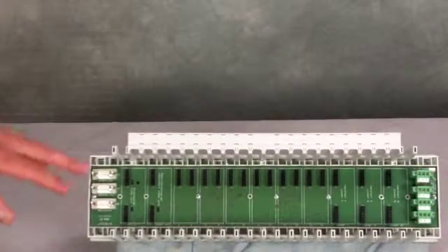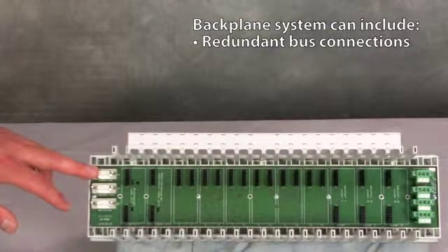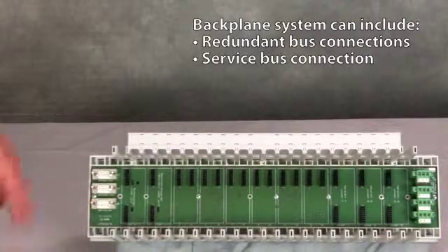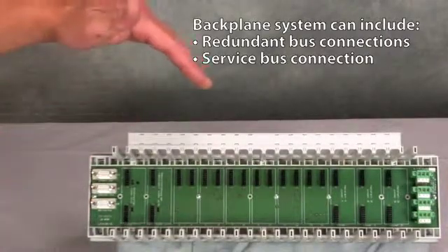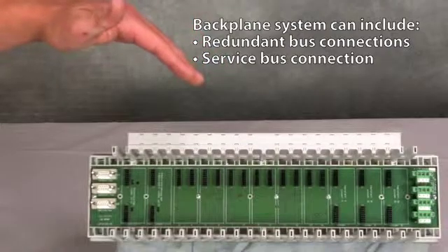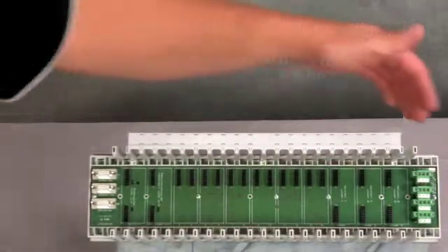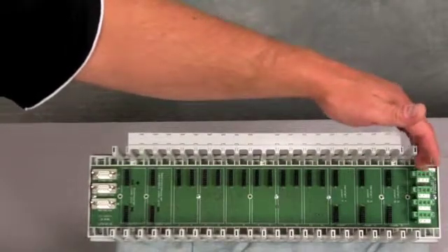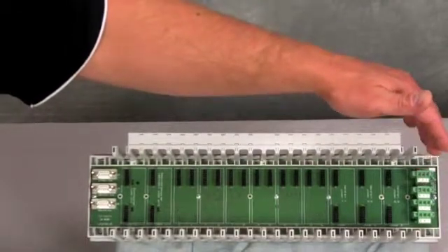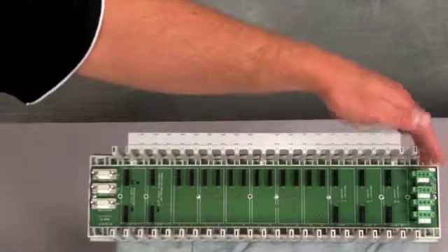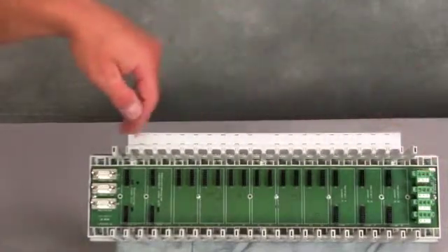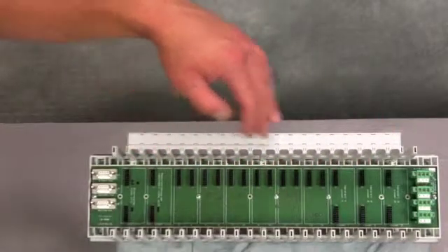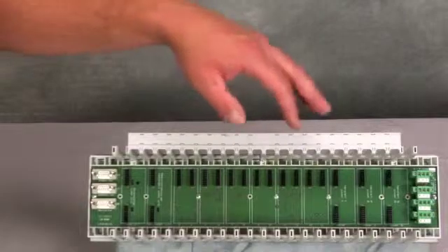The backplane contains redundant bus connections for the digital bus as well as a service bus connection which gives you access to diagnostic information from the different gateways and I.O. modules that are plugged into the backplane. And then on the other side you have your power bulk 24 volt connections as well as some additional power boost for digital outputs. And you can see here that you have different terminals along with guide rails for your different I.O. modules and power supply and gateway.